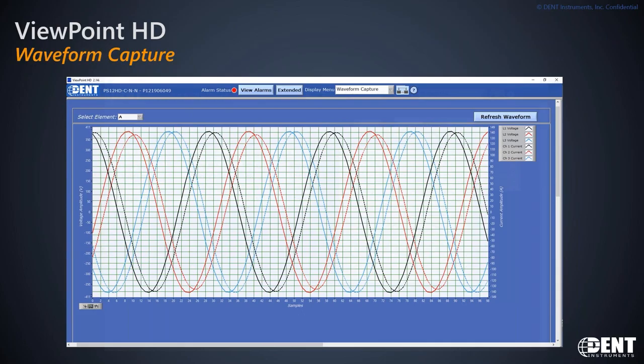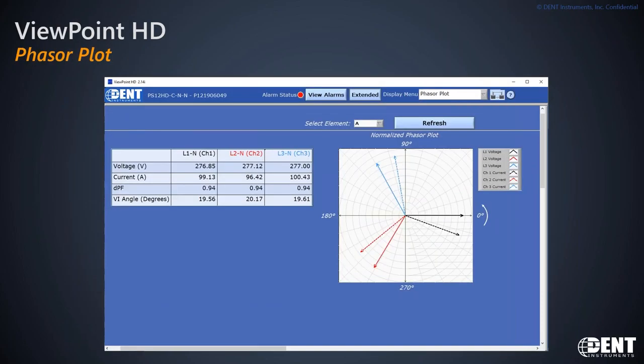The phasor plot is the primary tool I use to help customers confirm that they've phased the installation correctly. Each CT terminal on the meter needs to be associated with a voltage, and that process is often visualized as a rotating diagram called a phasor plot. Normally for industrial sites you would have a lagging power factor, meaning the currents would be slightly behind the voltage vectors, which is illustrated in the image. If you've misphased the meter, the dashed-line currents usually end up in the wrong quadrant, and this tool allows you to hot-plug those CTs back and forth until the image is correct.